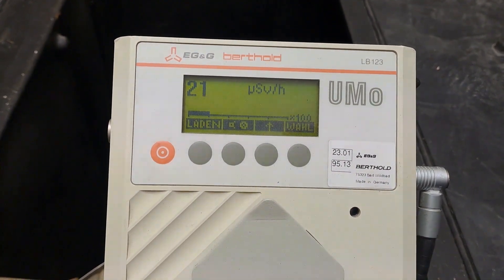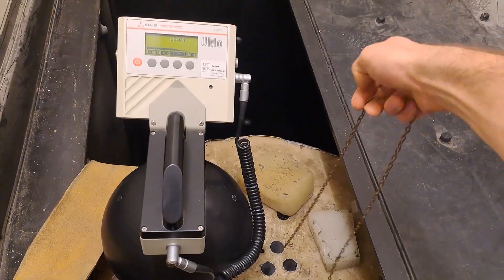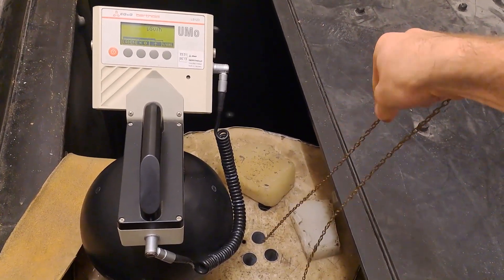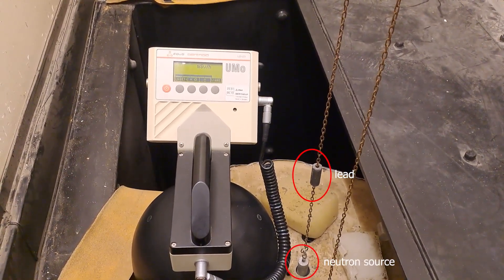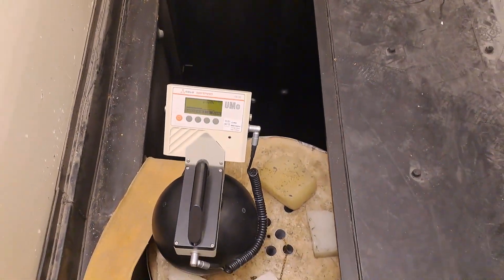For science, let's pull out the neutron source and measure a crazy contact dose rate of pure neutron radiation. It comes out to about 1 millisievert an hour, just from neutrons. Off-camera and with a bit of tweaking, I got up to 1.5 millisieverts an hour. And of course, I've never touched the source directly. 20 millisieverts an hour from prompt gammas comes in addition to that, but this is just because we don't have devices that measure higher.